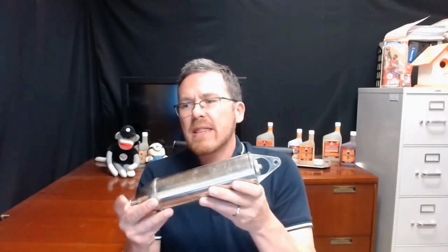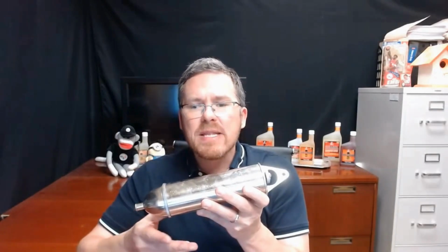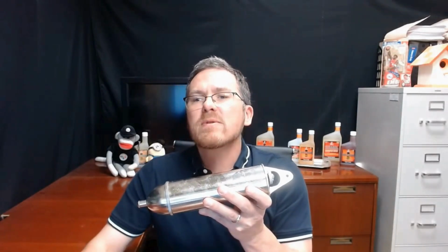But we would actually recommend not using a sampling port like that, because if you do, you don't have any control over exactly how far down or exactly where your sample's actually coming from. What you really need to do, and this would be the recommendation, is you need to use a fuel sampler, sometimes known in the industry as a bacon bomb. Now, a bacon bomb is a non-sparking metal cylinder, and it looks something like this. And this is probably the most commonly used thing for taking fuel samples in the industry.